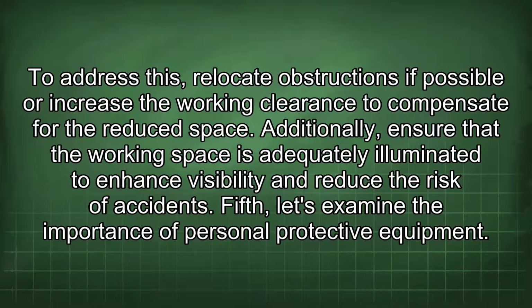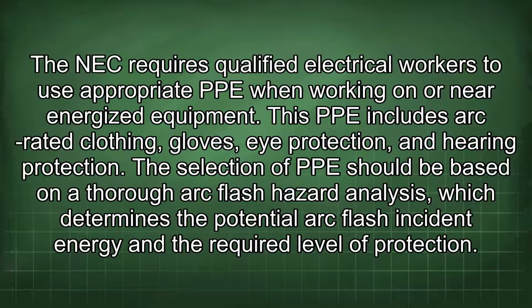Fifth, let's examine the importance of personal protective equipment. The NEC requires qualified electrical workers to use appropriate PPE when working on or near energized equipment. This PPE includes arc-rated clothing, gloves, eye protection, and hearing protection. The selection of PPE should be based on a thorough arc flash hazard analysis, which determines the potential arc flash incident energy and the required level of protection.